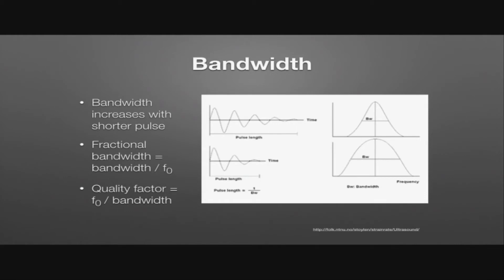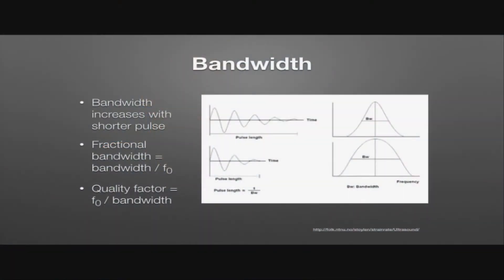The bandwidth is drawn around a central frequency known as the operating frequency. For instance, imaging probes like the abdominal probe operate at lower frequencies compared to a linear probe operating at higher frequencies. Although we describe a single operating frequency, what's actually happening is that a range of frequencies is being transmitted. We describe the fractional bandwidth as the bandwidth divided by the operating frequency, and the quality factor as the operating frequency divided by the bandwidth.